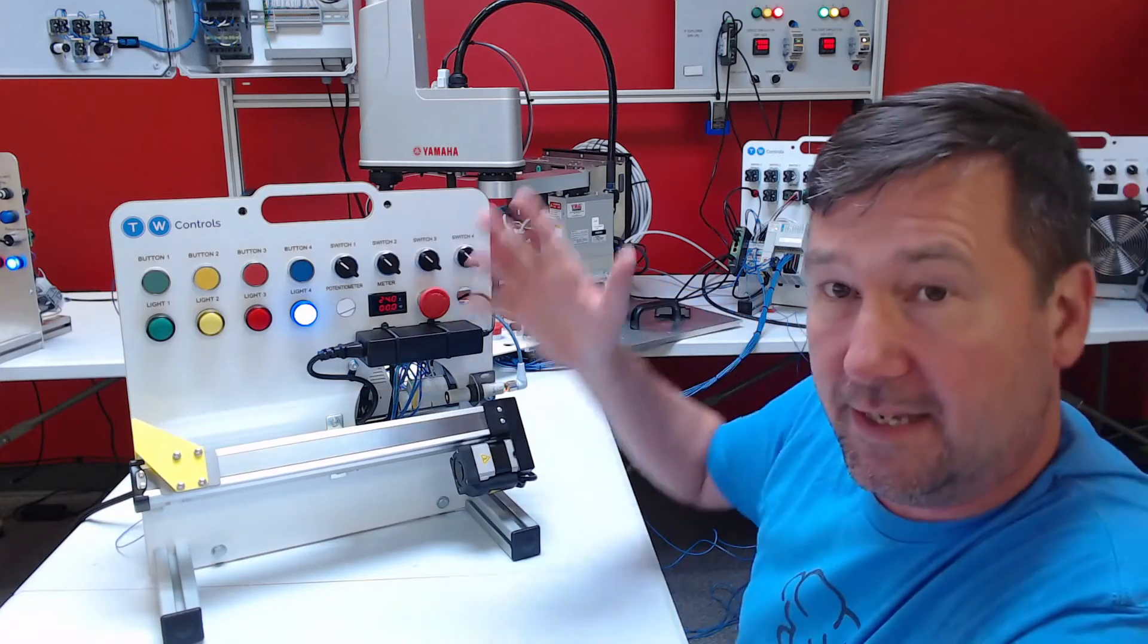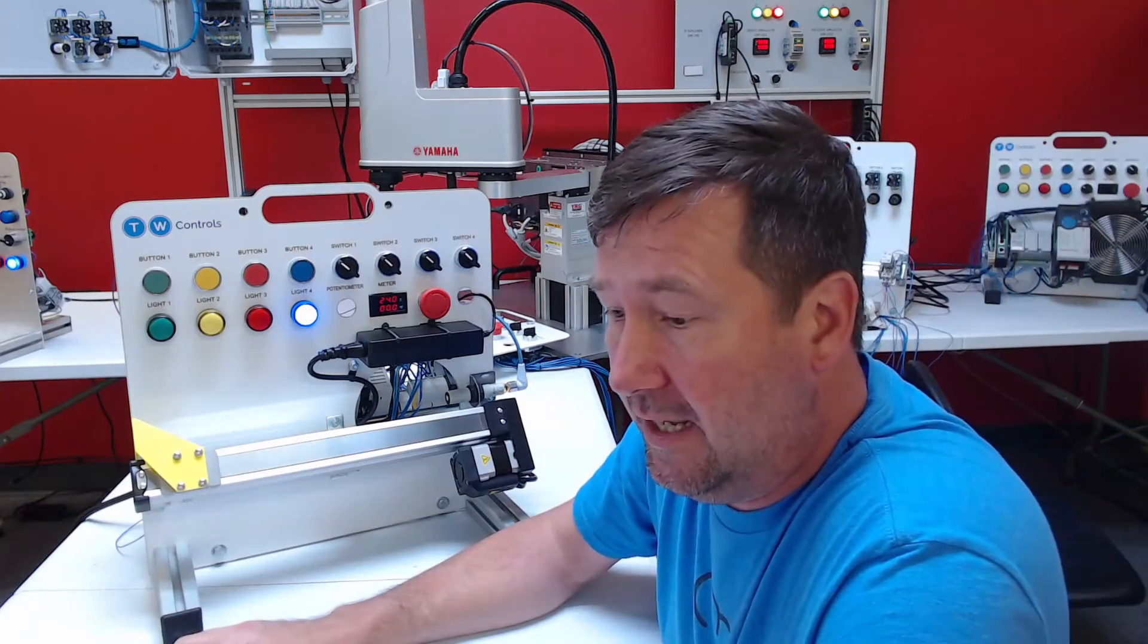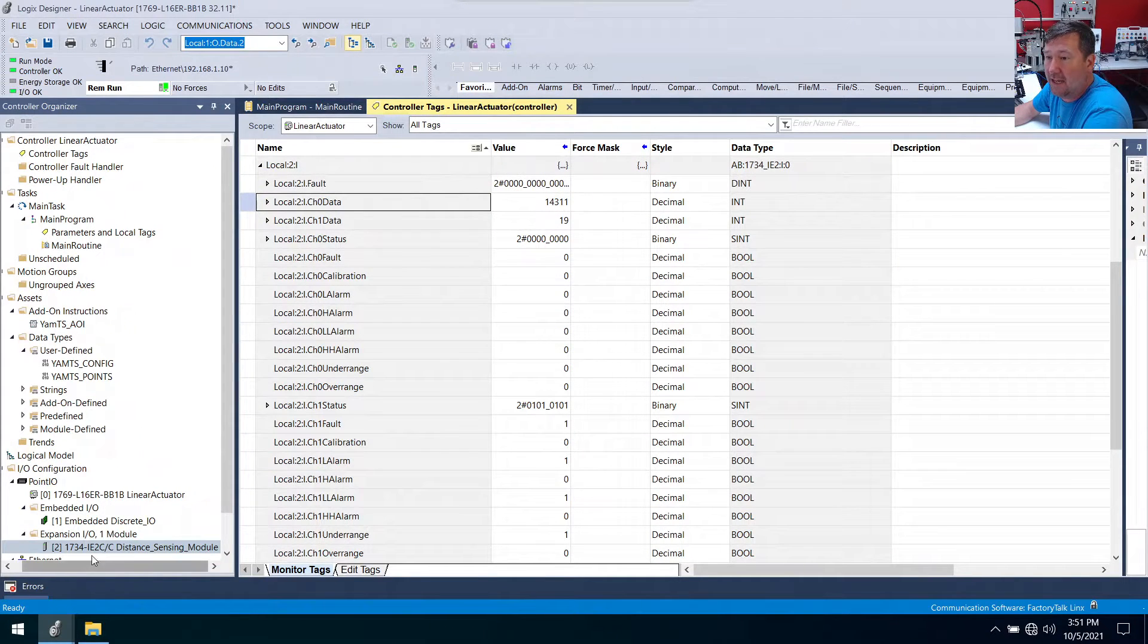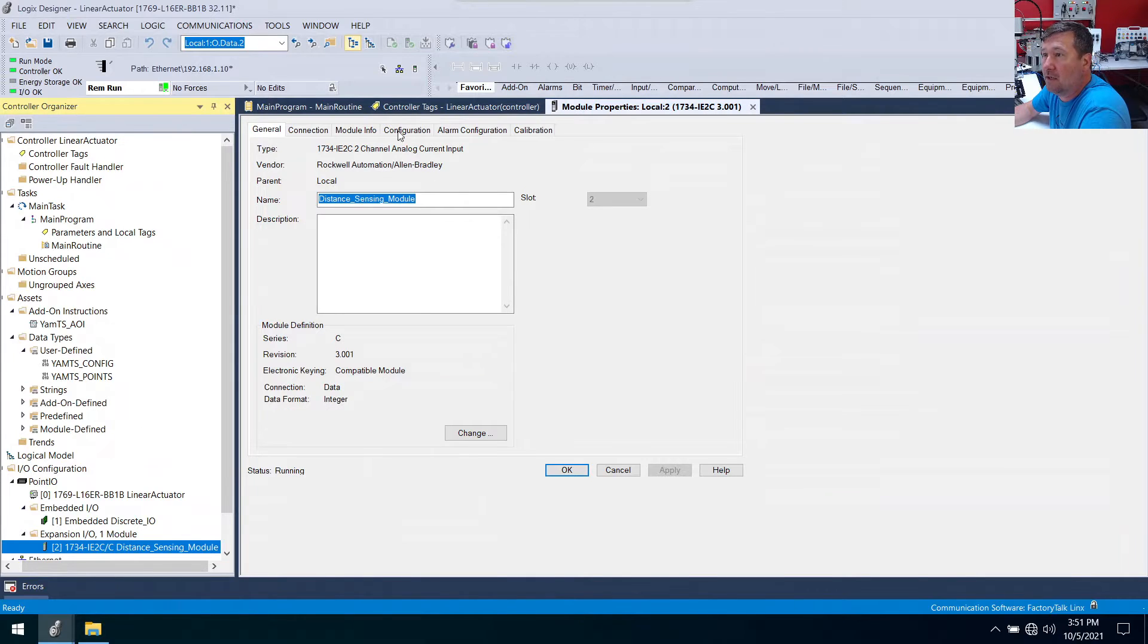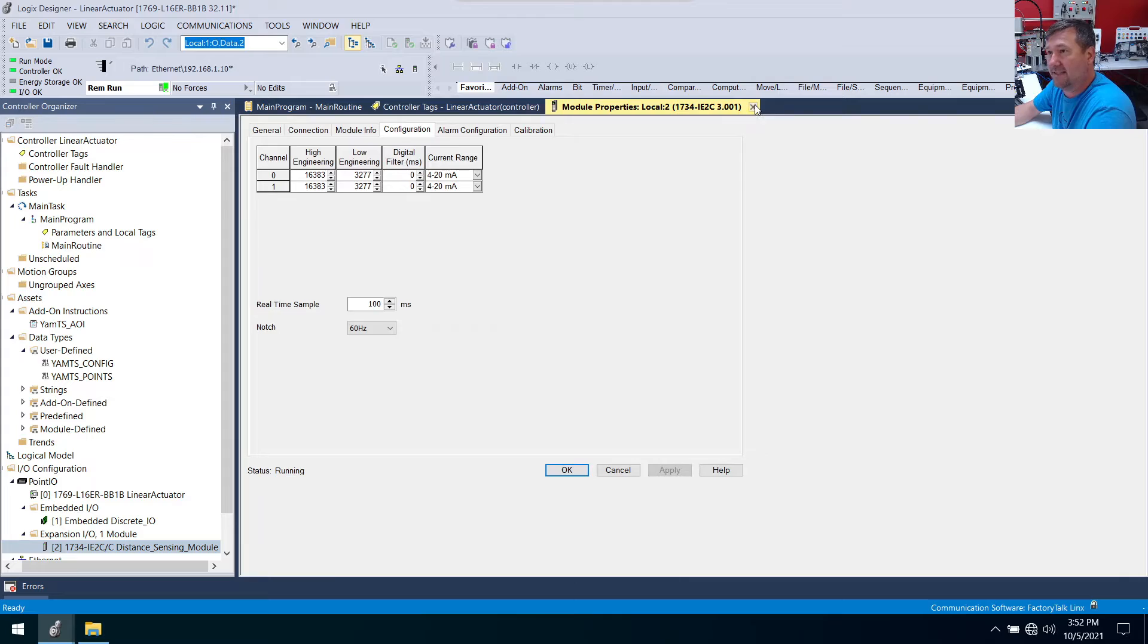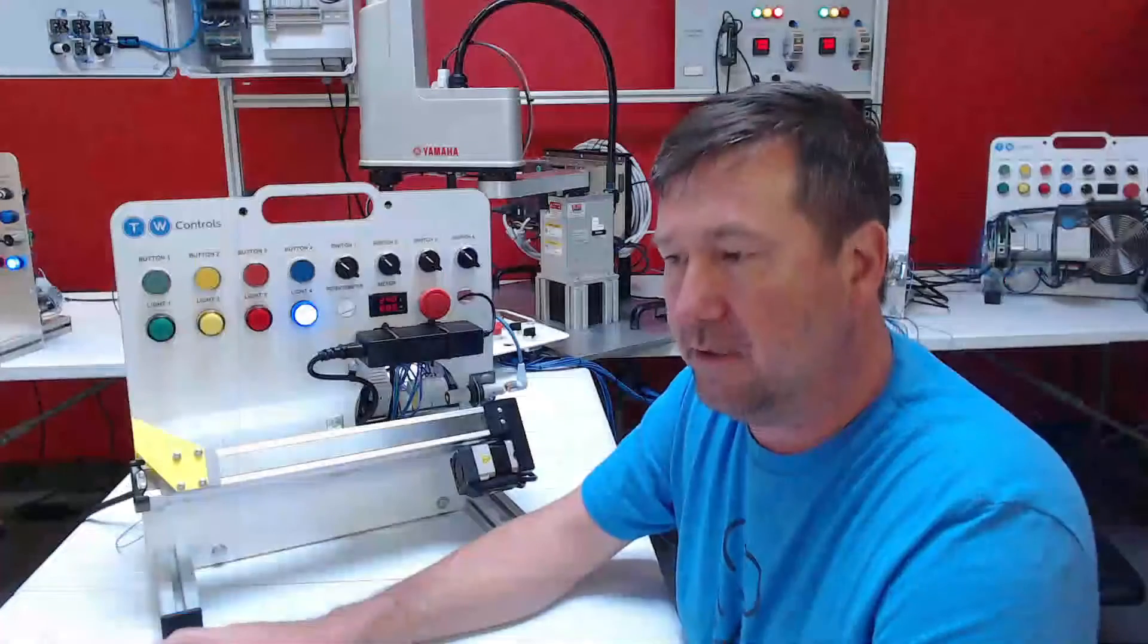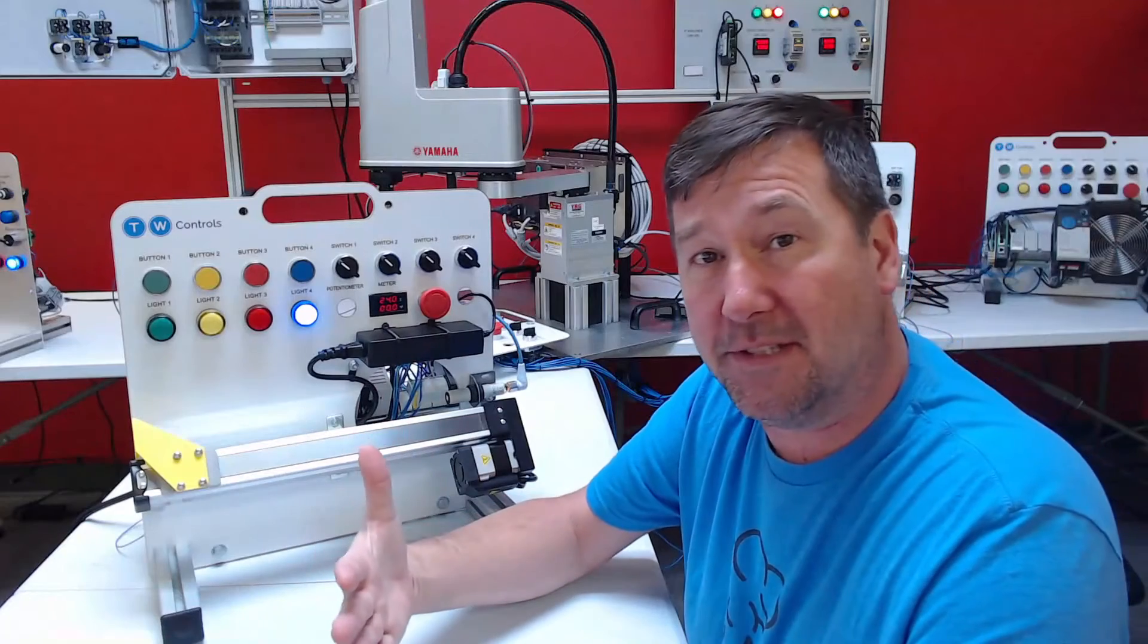So I am still in hand. I should be able to switch switch three to the left. All right. And that took it all the way to the other end. And if we look now we're at 14,289, which remember our 20 milliamp value was 16,383. So we're a little less than 20 but we're pretty high up there.